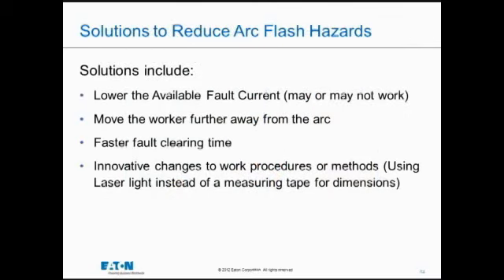When we look at solutions, how do we get the arc flash hazard lower? These are the 4 items that come up. If you go back to that equation, it's the power of the arc. How powerful is the arc? Well, if we can reduce the short circuit current, we could make the arc less powerful.